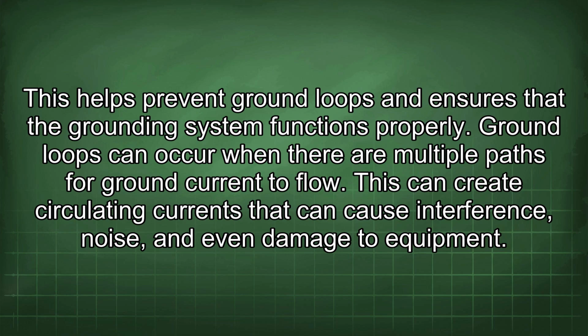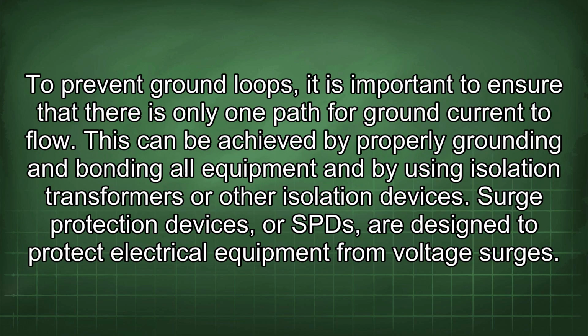Ground loops can occur when there are multiple paths for ground current to flow. This can create circulating currents that can cause interference, noise, and even damage to equipment. To prevent ground loops, it is important to ensure that there is only one path for ground current to flow. This can be achieved by properly grounding and bonding all equipment and by using isolation transformers or other isolation devices.